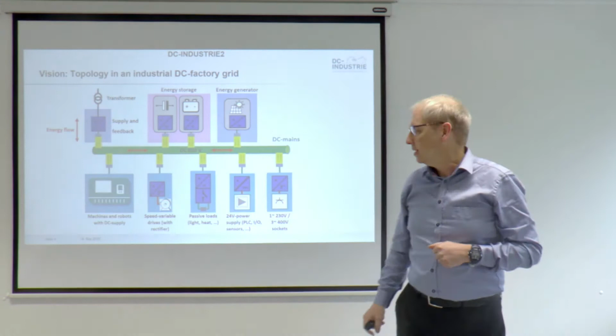There are a lot of advantages of DC grids for industrial plants. You have a rising energy efficiency because the transformation losses are reduced. Also, you have a lower copper, which means that you can reduce the transport losses in the DC grid. On the other hand, you can directly use renewable energy sources like a solar module on the roof of the factory. And another advantage is that you can reduce the peak power of the factory by the use of these storage systems.